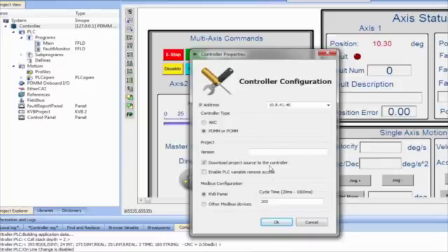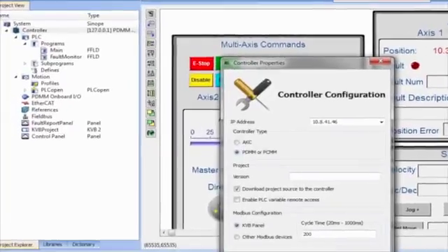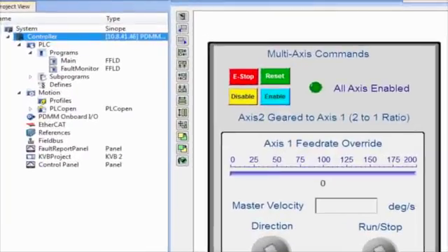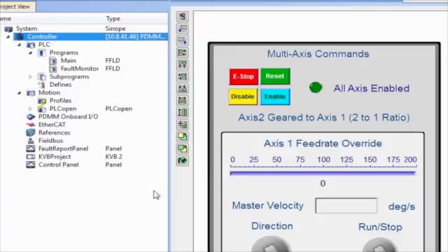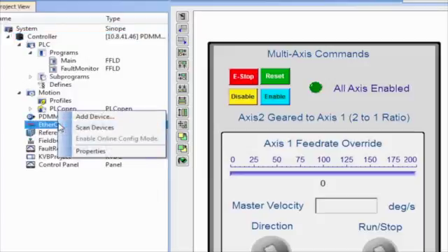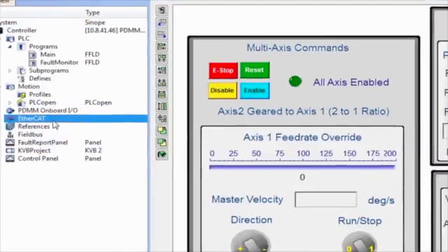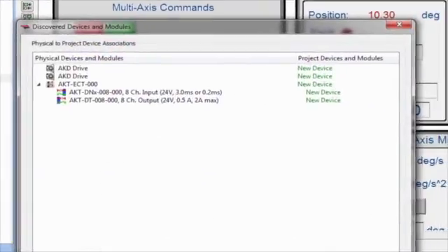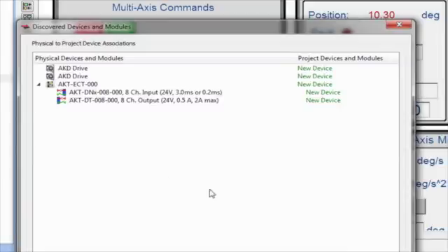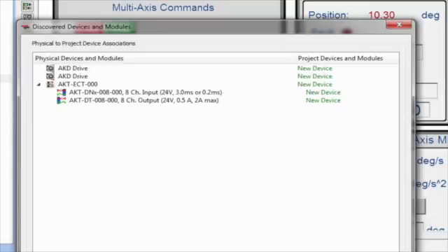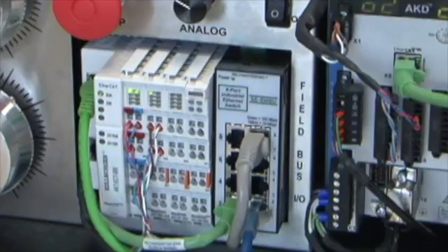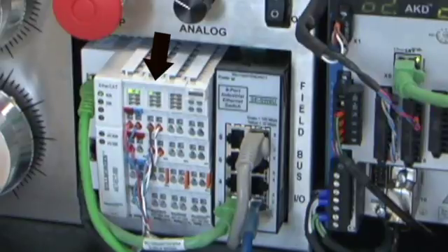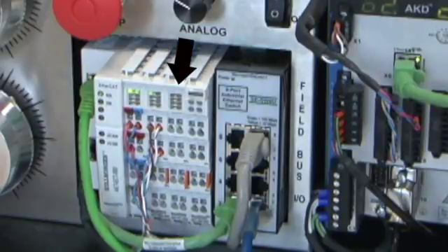Then, the EtherCAT network must be defined. This can be done in the EtherCAT section of the project tree. By right-clicking and selecting Scan, all components connected to the network will be found. In this case, there are two drives, one in the PDMM and the other an AKD-P drive. Also connected is a remote I-O coupler with an 8-channel input slice and an 8-channel output slice.